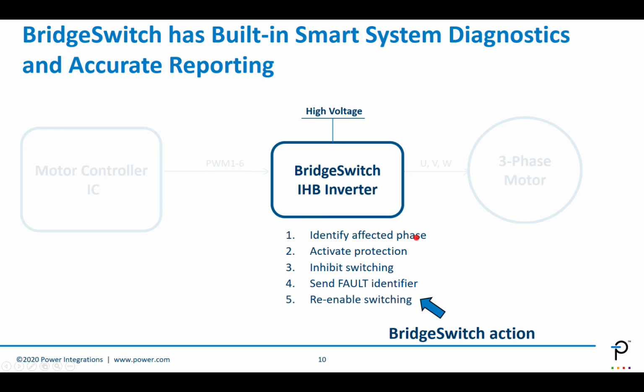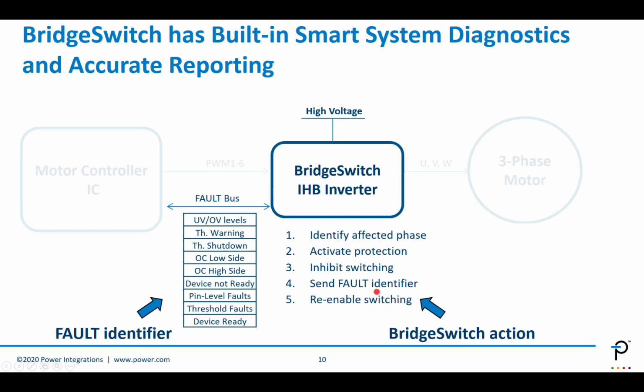BridgeSwitch will identify the affected phase in case any of the previously mentioned faults pop up, activate protection, inhibit switching, send a fault identifier, and then re-enable switching. It also sends over the diagnostics bus up to 9 distinct messages: UV, OV levels, thermal warning, thermal shutdown, the low side and high side overcurrent, pin level faults and threshold faults like we talked about for the vibration sensor, but also insights into the readiness of the inverter, device ready or device not ready.